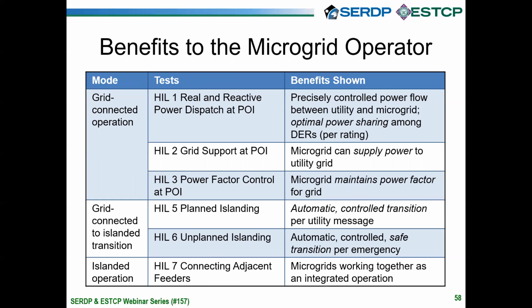In the second test, which I haven't shown the results of, we can support the grid. The microgrid can supply power to the utility grid if necessary, and we are able to control that. We can also do power factor control, and with the help of the microgrid we can influence the phase angles. So the power factors are as necessary.